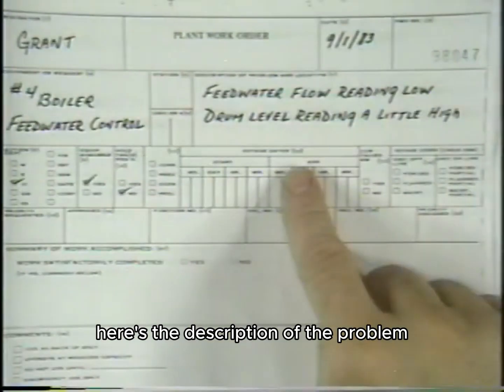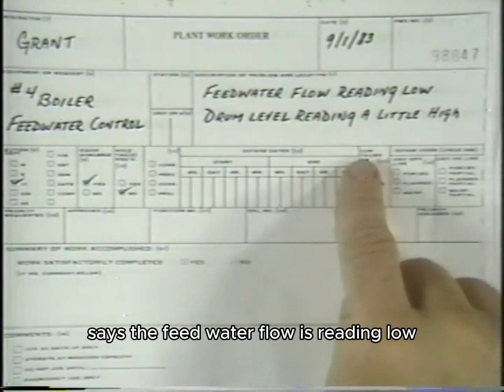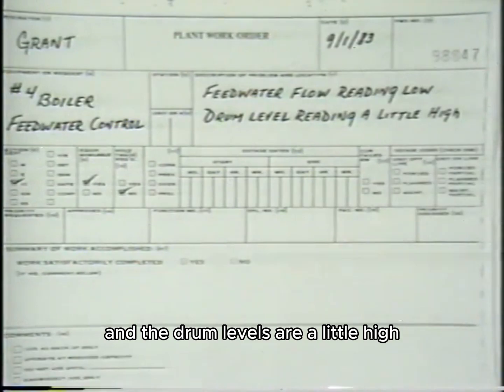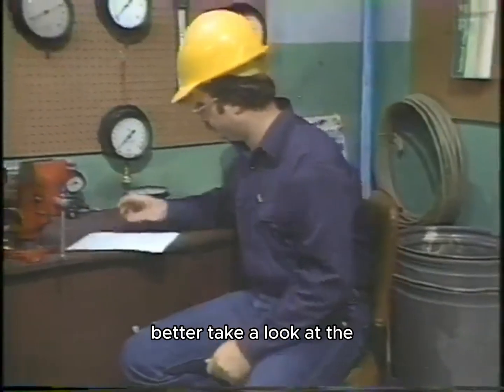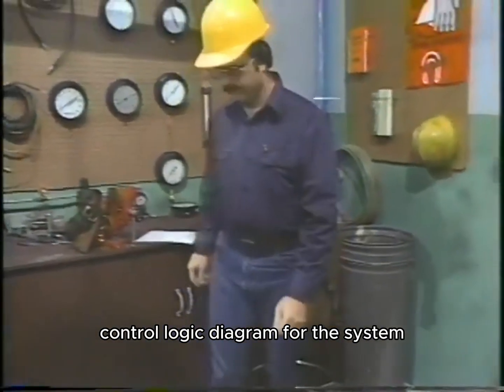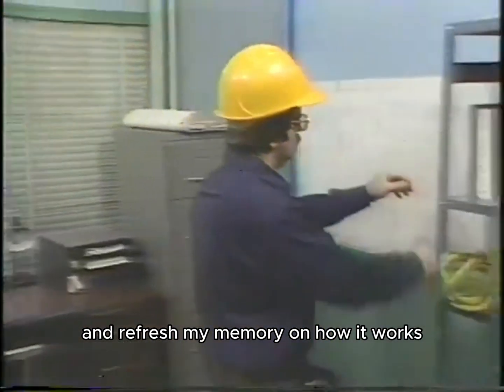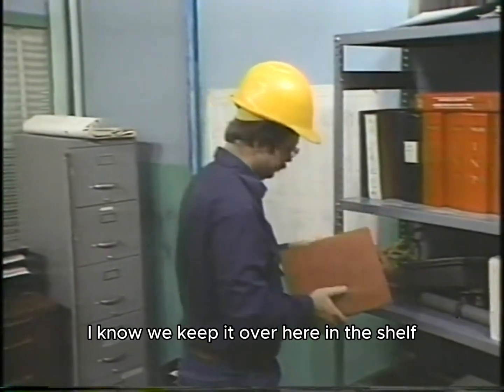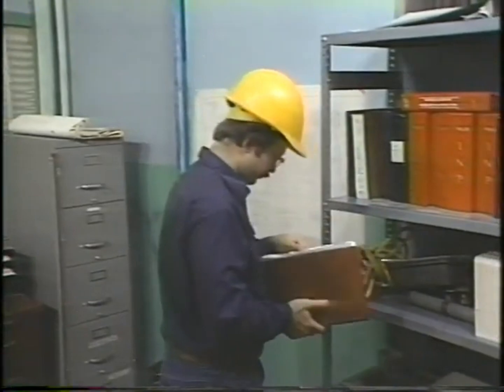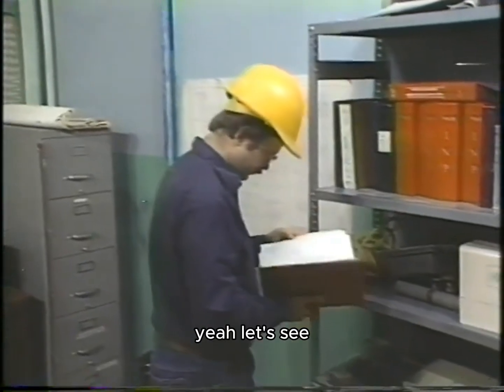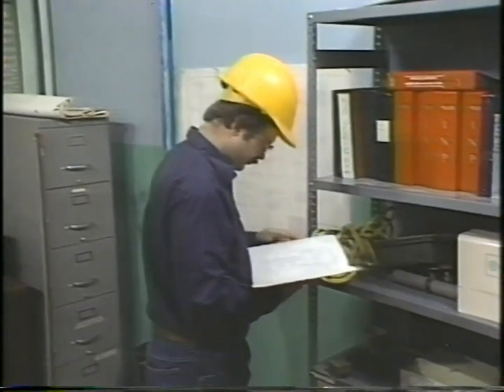Here's the description of the problem. It says the feed water flow is reading low and the drum level's a little high. Better take a look at the control logic diagram for the system and refresh my memory on how it works. I know we keep it over here on this shelf. Yeah, let's see. Here it is.